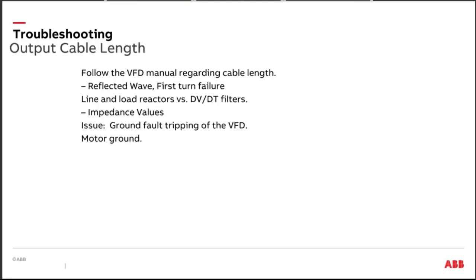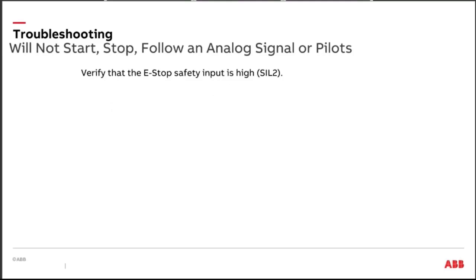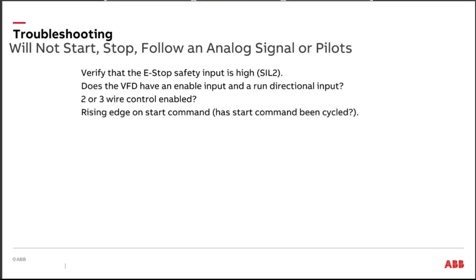I think one of the most common things that I ever got as a troubleshooting question is, I'm telling the drive to start and it's not starting. Every once in a while, we might get somebody call in and say, I've got the drive started and it's not responding to my stop signal. That happened too from time to time. And there's a couple of things that we need to do. And I can tell you, with the generation of drives that we have in the marketplace today, we really made troubleshooting this a lot easier, okay?